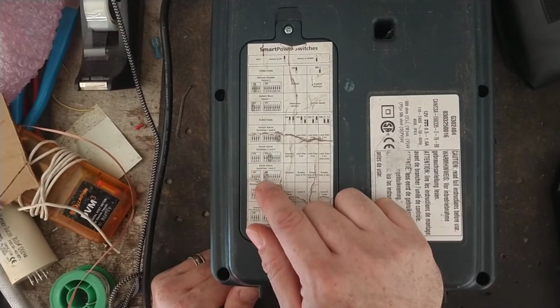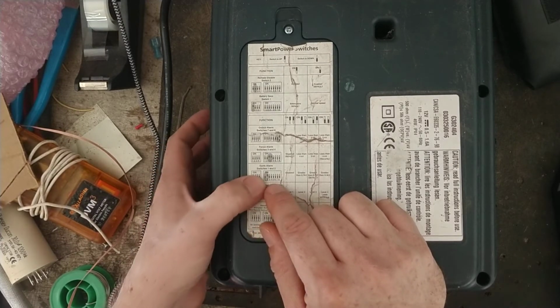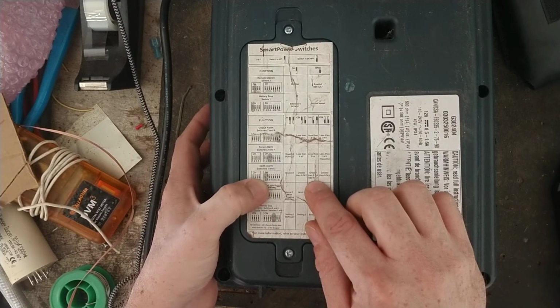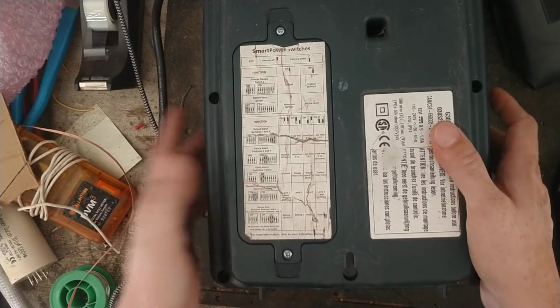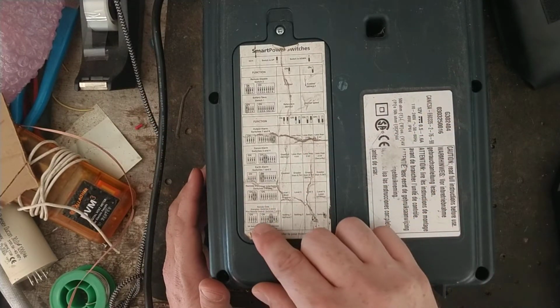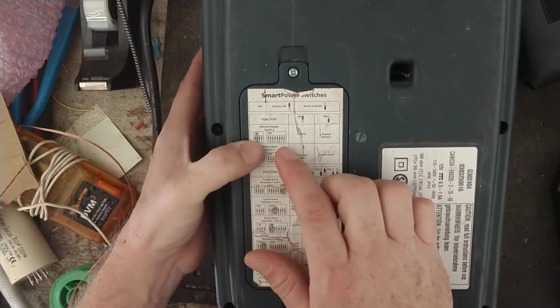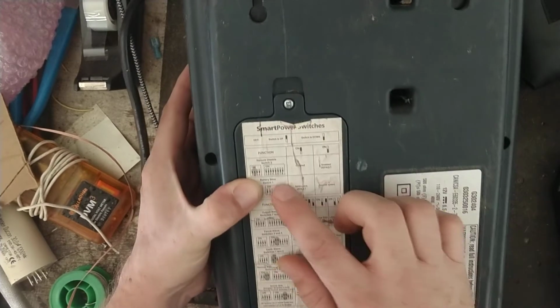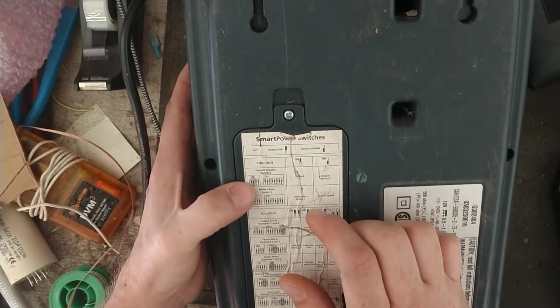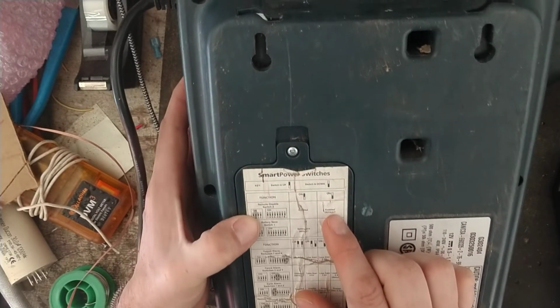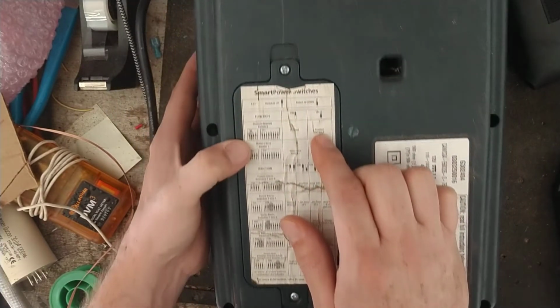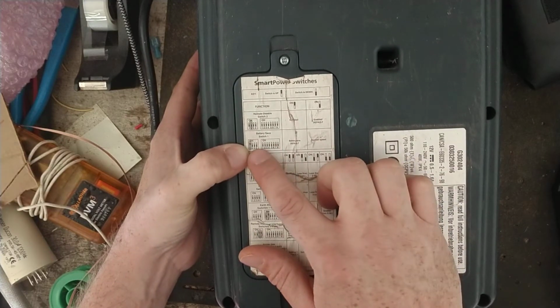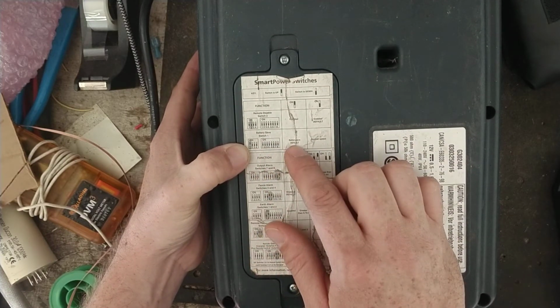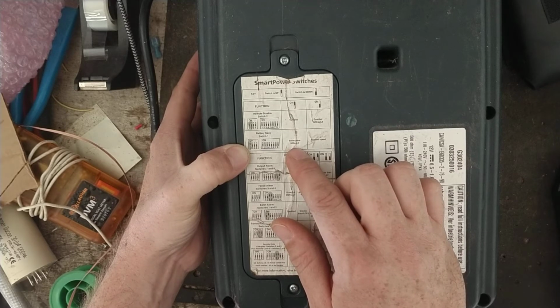Earth alarm is switches 1 and 2 on the set of 8. And default setting is 1 down, 2 up, and he's got 1 down, 2 up, so that's still the same. So earth alarm's fine, or that's what he set it at. And then there's a remote control enable disable up here. It's switch number 2 on the set of 4, and down is enable, which is a default setting, which it's set to down, which I would think it should be. Switch 1 on set of 4 is battery save, and it is set to default of battery save.